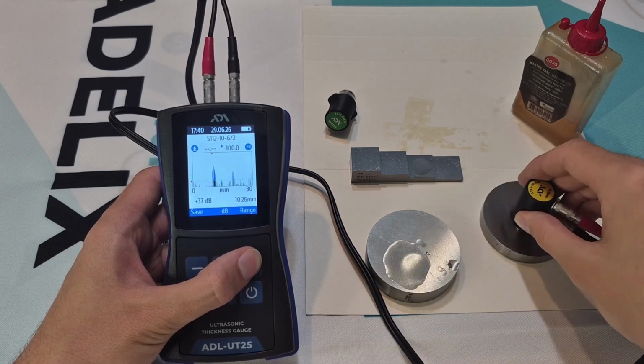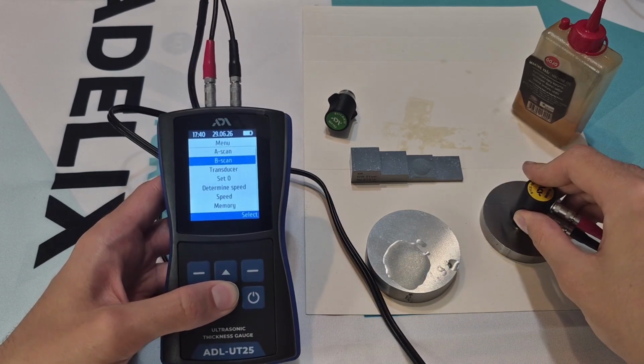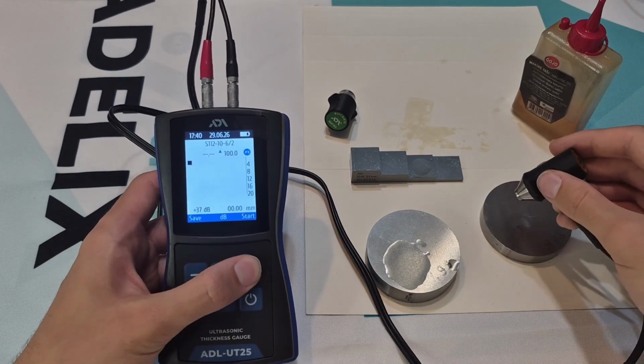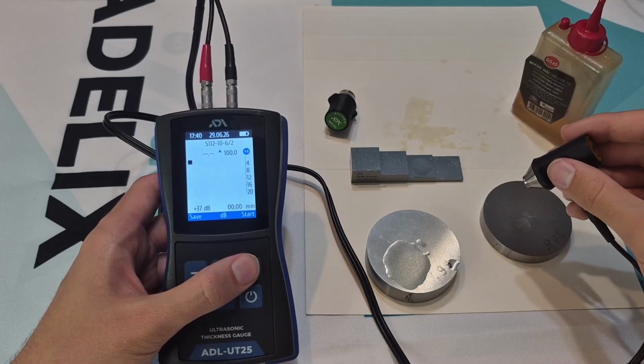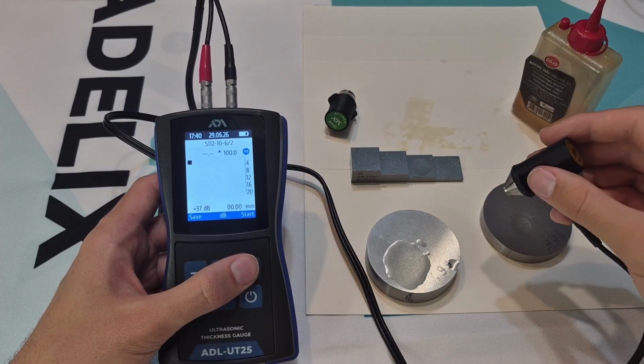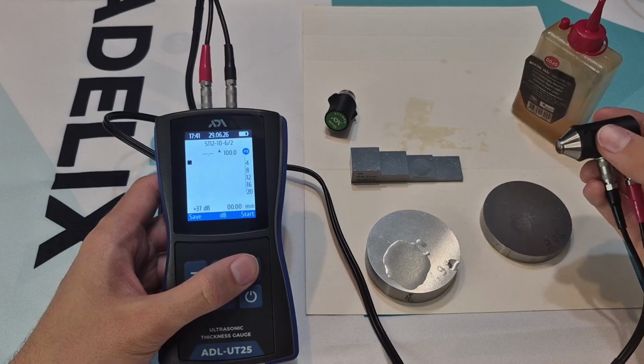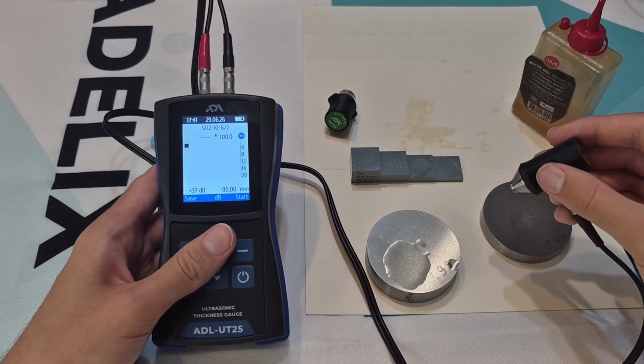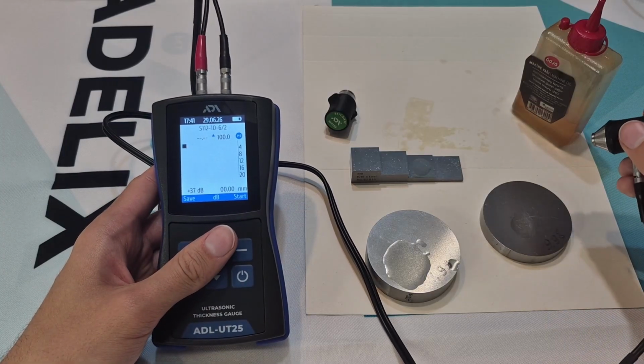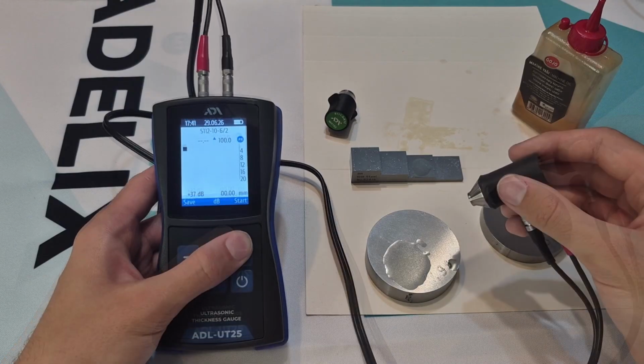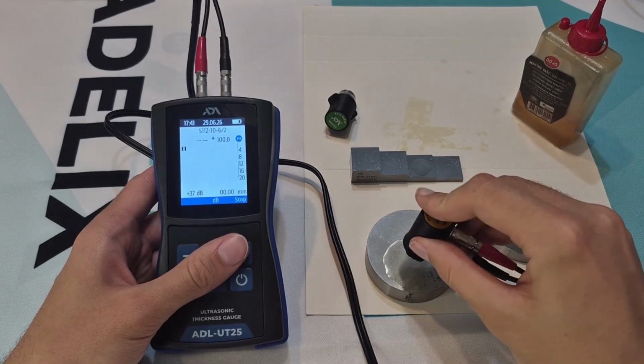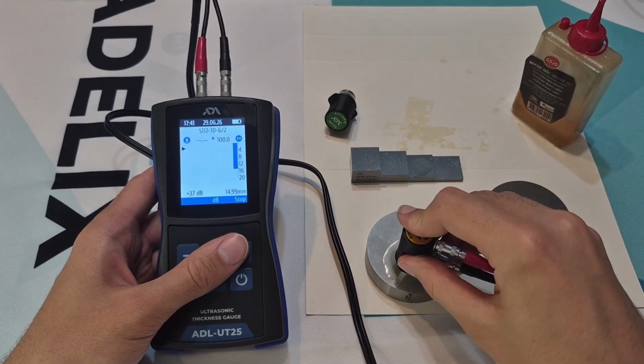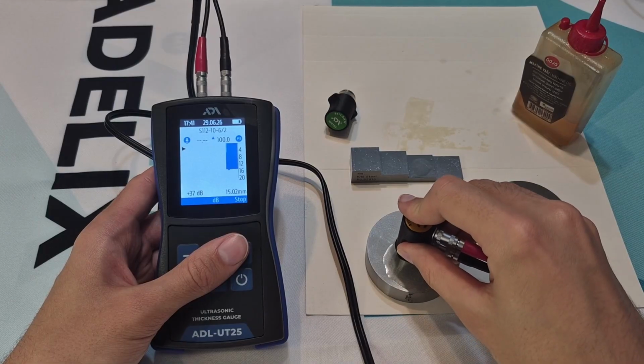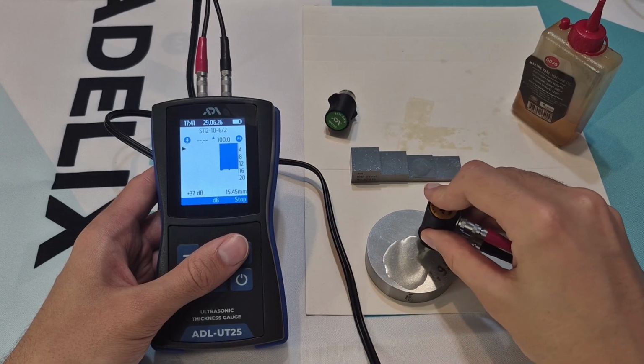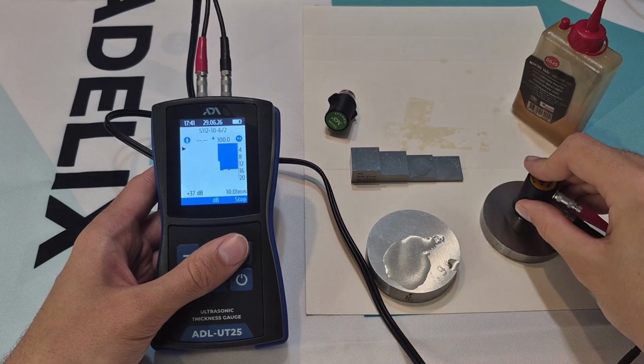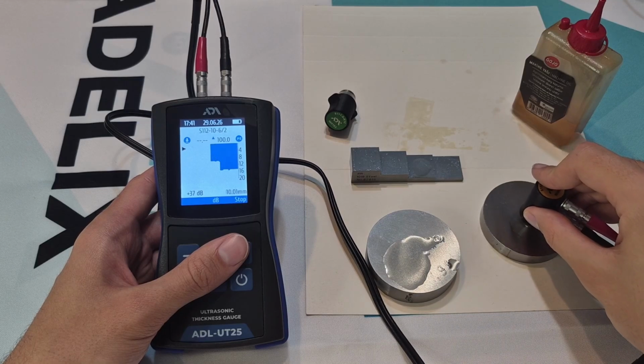The next mode is B-scan. It is designed to monitor wall thinning in parts such as pipes. During operation due to corrosion or wear, the wall thickness of a pipe may decrease. For monitoring, we start B-scan mode, press start and move the transducer along the surface. The device continuously records the thickness profile. If wall thinning occurs at any section, it is immediately shown on the screen. This way, problem areas can be quickly identified and the necessary measures can be taken in time.